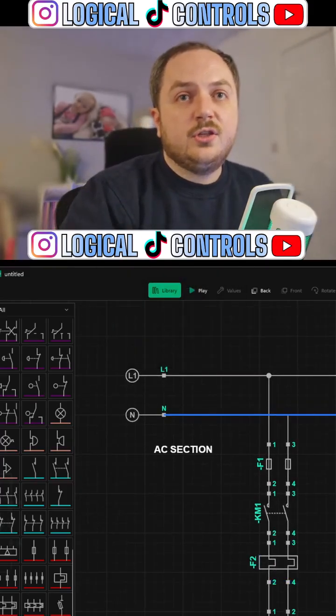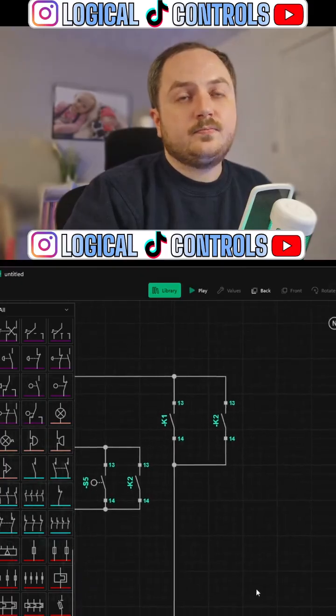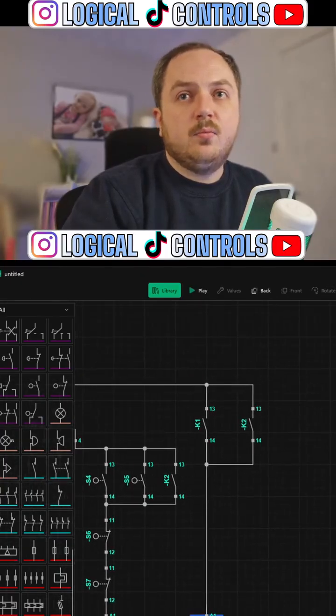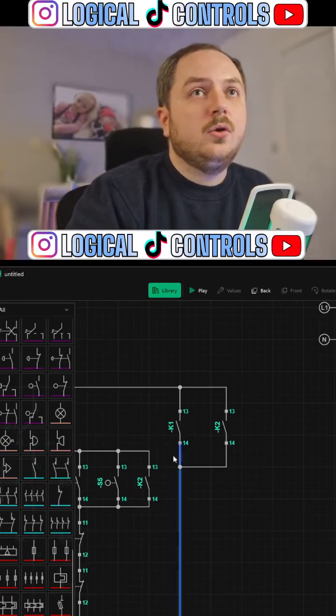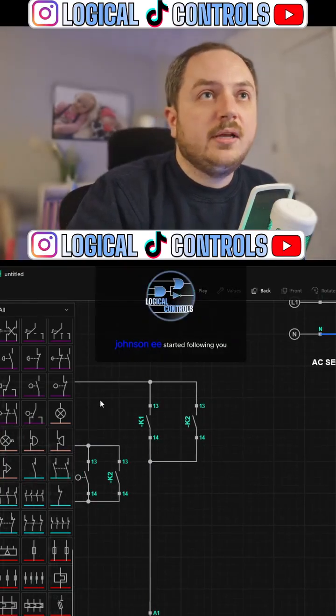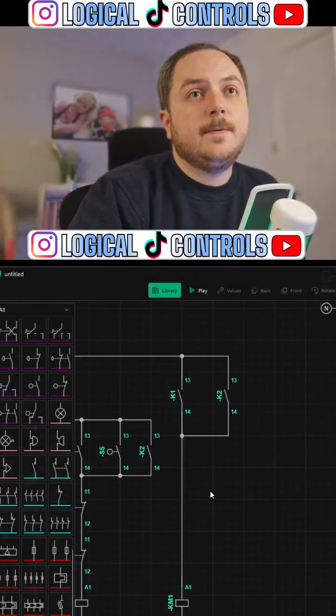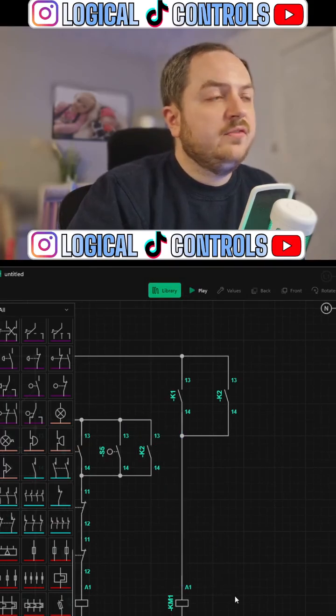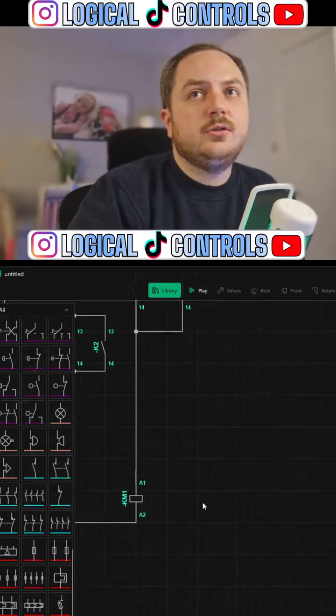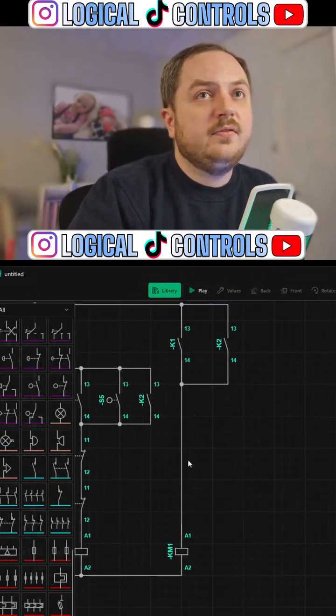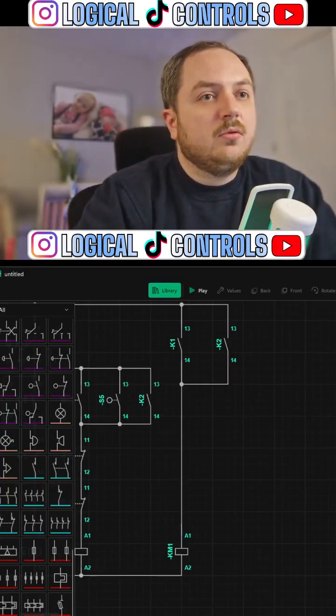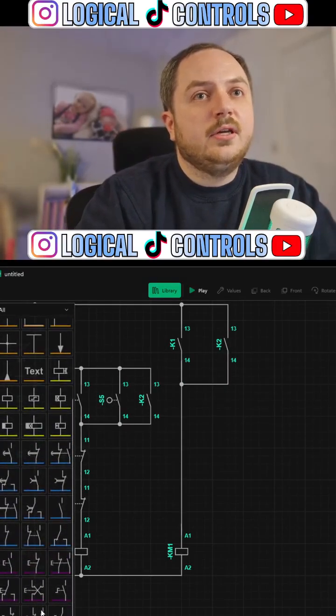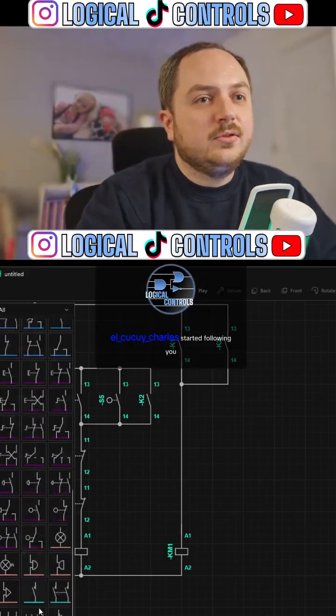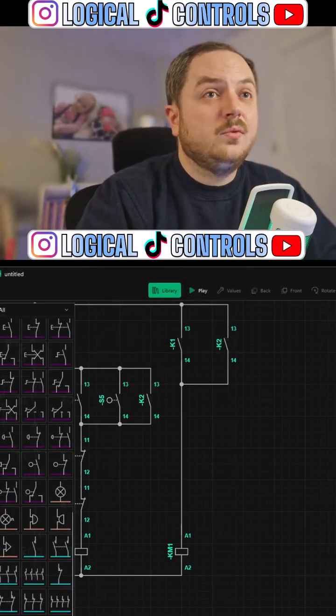Right, okay, so we've got an F2 and an F4. That's what I need to know. So that's my pump 1 command. All I really need to do now to get the standby to run, oh my mistake, is come off this point here, tap off through my overload contact into KM2's coil, I believe. That's what I'm going for anyway. We're gonna run with it. I'm just making this up on the fly. I've not planned this or nothing. So we'll do that because I think that's gonna work, and if it doesn't, we'll work from there.